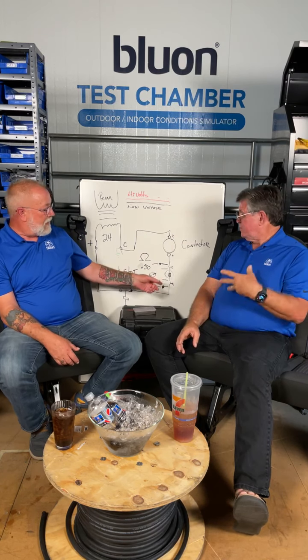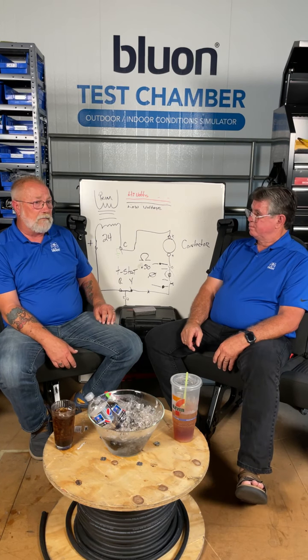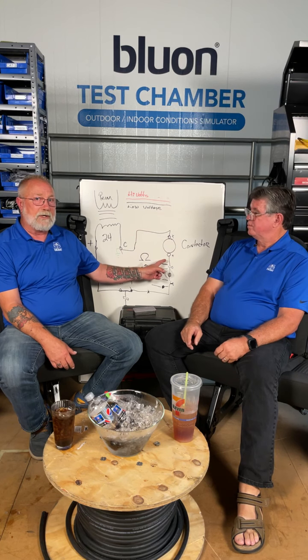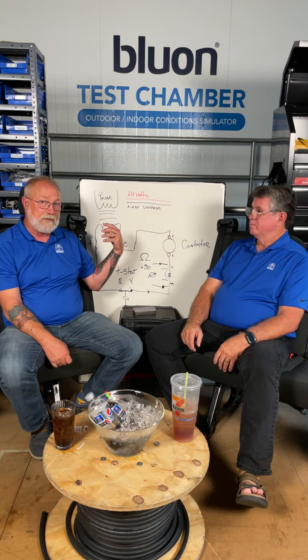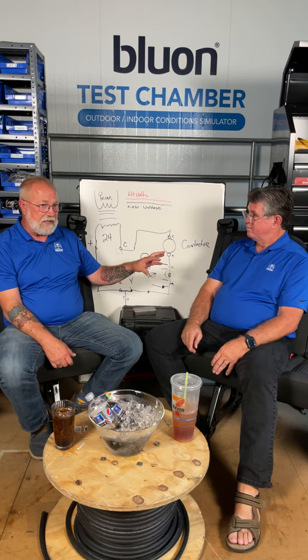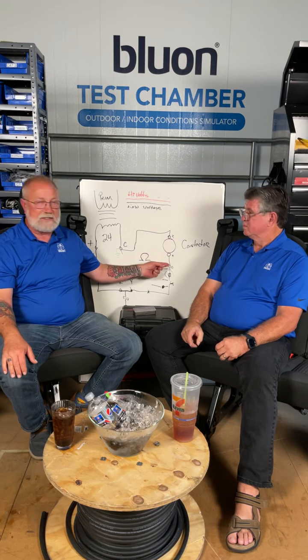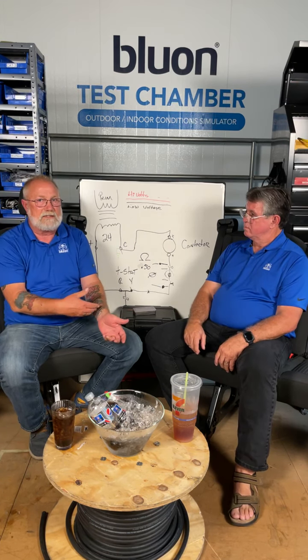Yeah, and guys, you don't have to be at the switches. If you look at the boards, the defrost boards, the low pressure and high pressure switches come back to the terminals on the board. Like Mike is saying, I can already visualize where he's at working on a machine. Everything comes back into the control panel, and you can do tests hot. You're not going to be able to reach into a 5-ton condensing unit and take voltage readings at the actual pressure switches, because you can't get past the running condenser fan motor unless you're real fast. That'd be super fast.